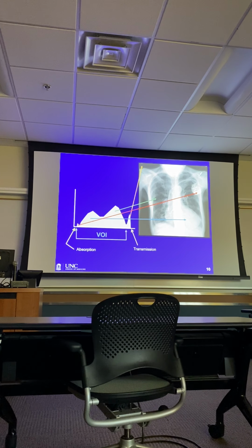So whenever you make an X-ray exposure, it's creating a histogram, okay? It will look at models in the system and compare your model to decide where it should drop these values of interest. It looks at the peaks and the valleys and decides where to drop those values that need to be included in processing.